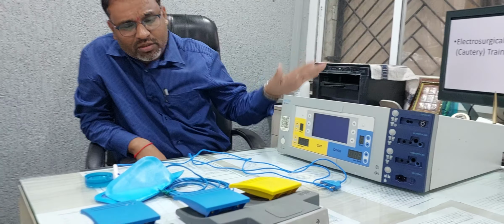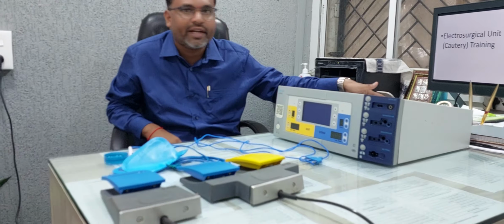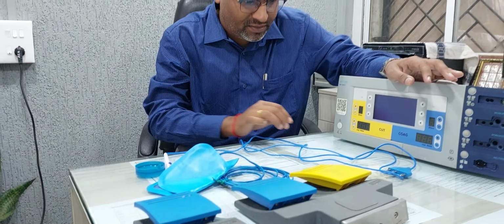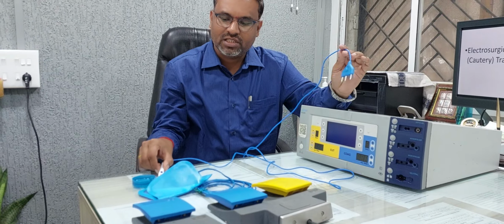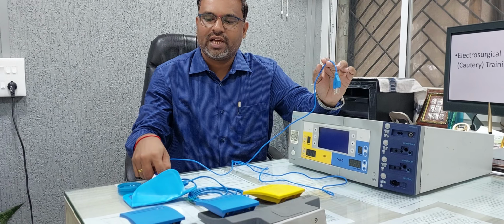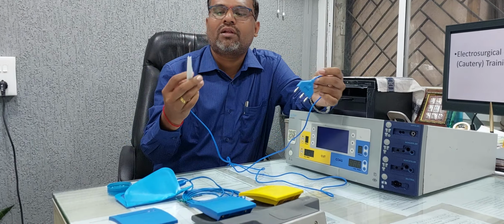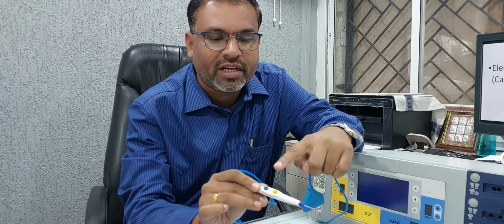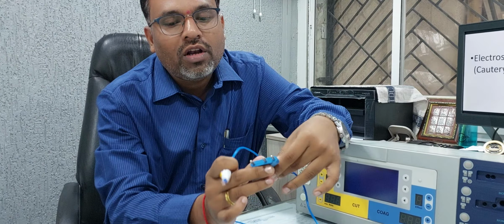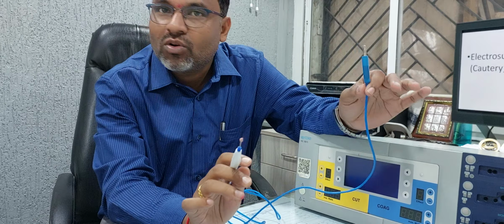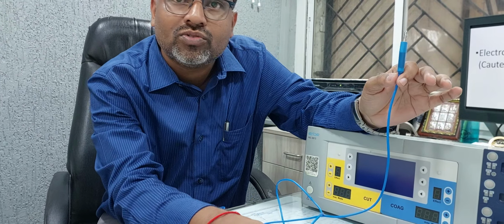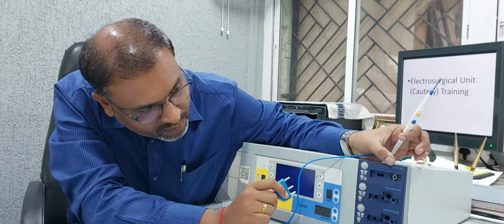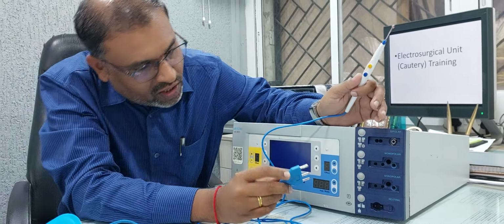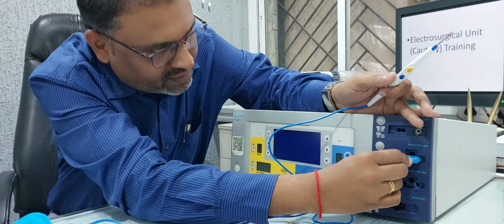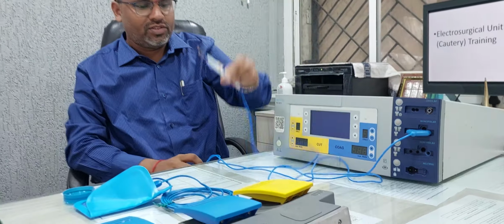So first, I will show you what are the basic connections we have to make. First, you have to connect the power cord, right? After that, see, this is nothing but your pencil, monopolar, bipolar pencil, like that. It has two modes, cut and coag. For all types of cautery, there is a universal coding. Yellow is for cutting and blue is for coag, right? So see, here you can observe bipolar, monopolar and neutral. At the monopolar, you just connect this, right, in this way.